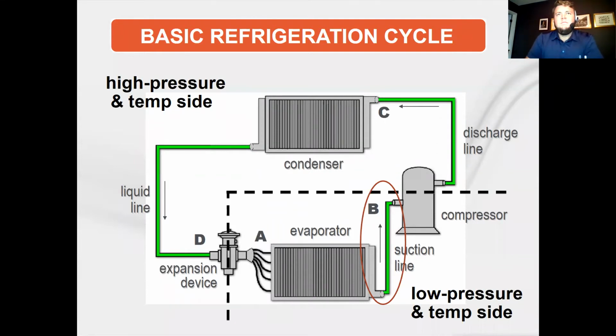Yeah, I appreciate it. And then we have another good question, Randy, by the way, in the chat right now in regards to the frosting condition. You mentioned the left side of the cross plot. The question is, aren't TXVs better than fixed orifice valves to prevent frosting under low load conditions? Yeah, you're not going to see any orifice probably in this type of a system, but in small residential systems, that's the cheapest way to do it. But it's like the questioner says, it's not very accurate, but it all depends on the type of system. But in a commercial system, you'll always see some kind of an expansion device that is either a mechanical valve, or more recent systems have electronic valves.